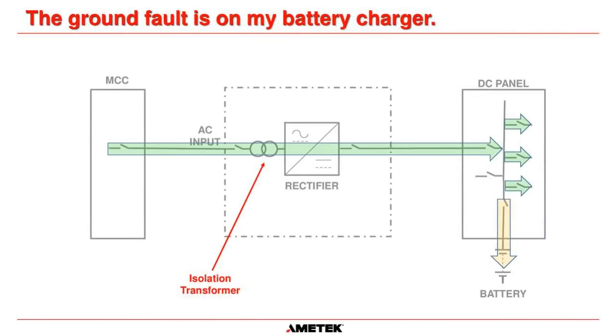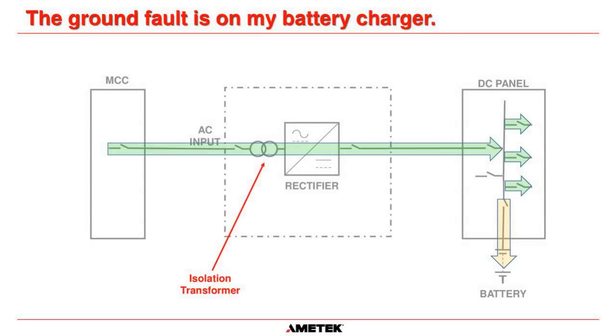So now we're going to move on. Another very common complaint I hear is that the ground fault is on my battery charger. I can understand why people think that, because for the ground fault alarm, there's usually a lamp on your charger that says ground fault. So everybody thinks that if the light comes on the charger and says ground fault, then the fault is on the charger.